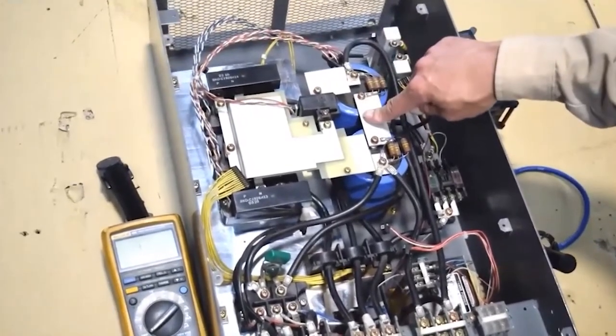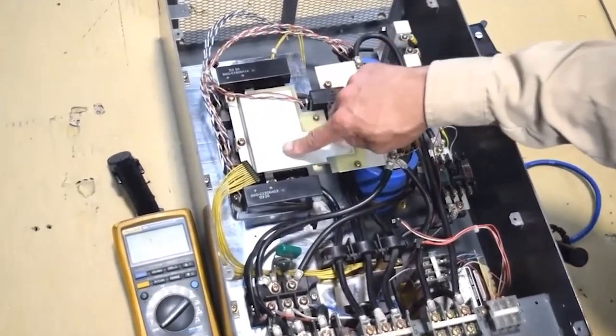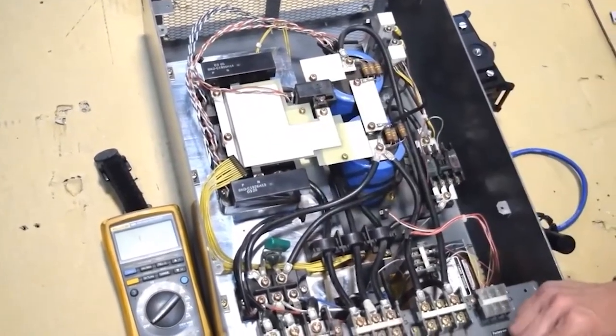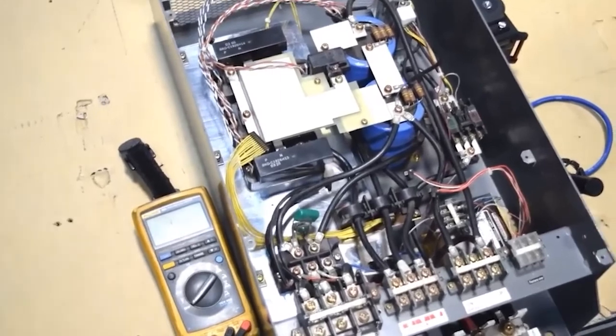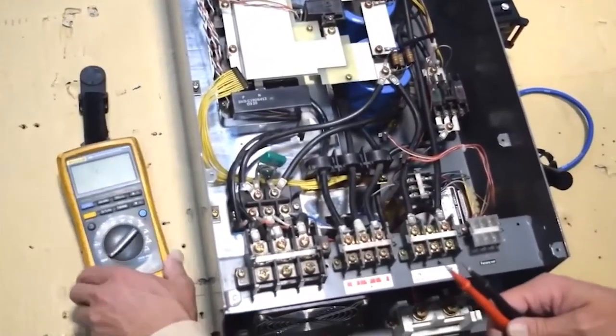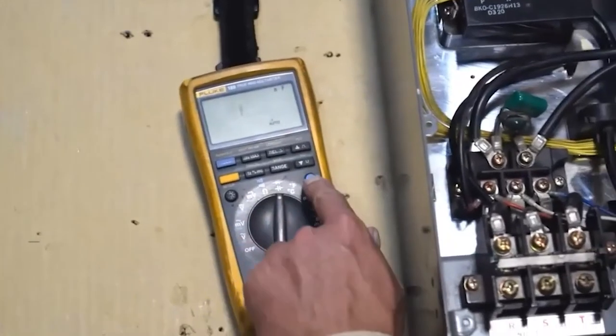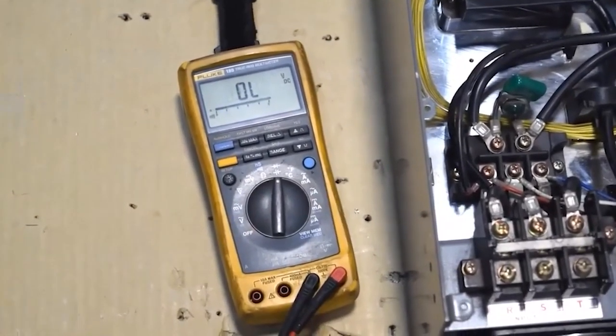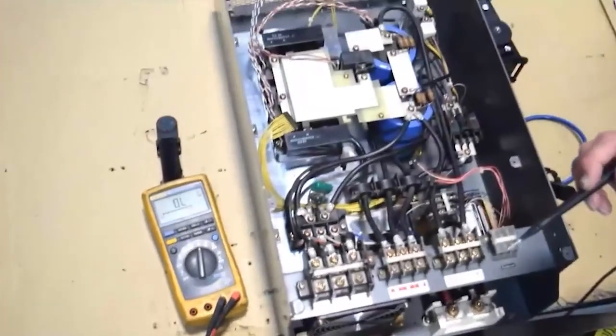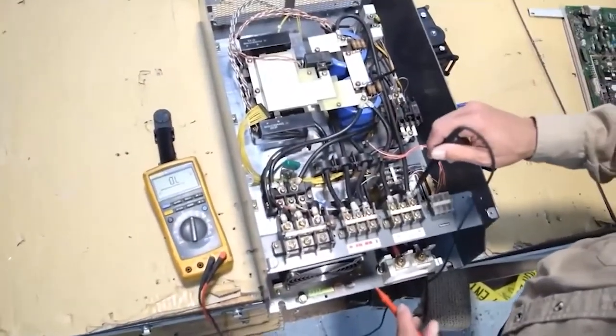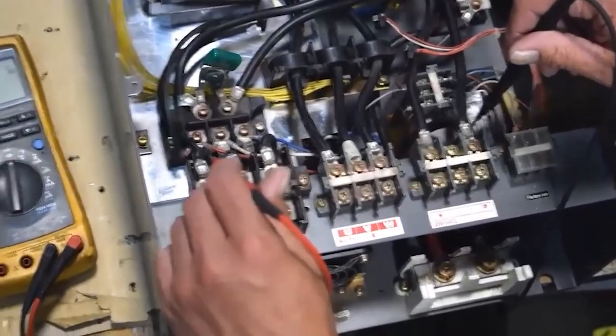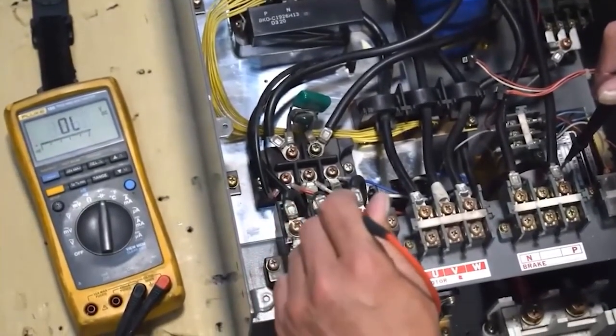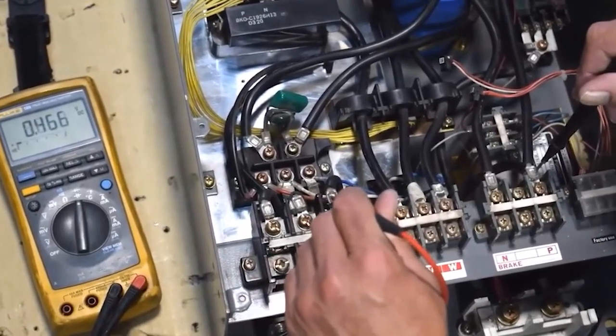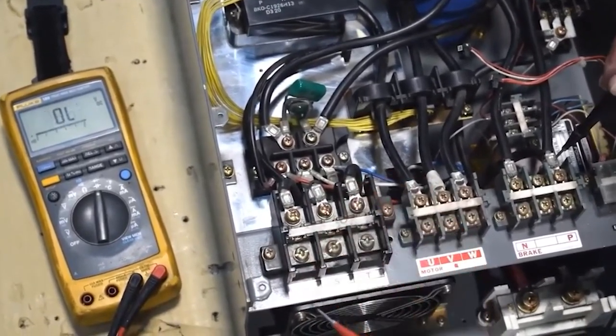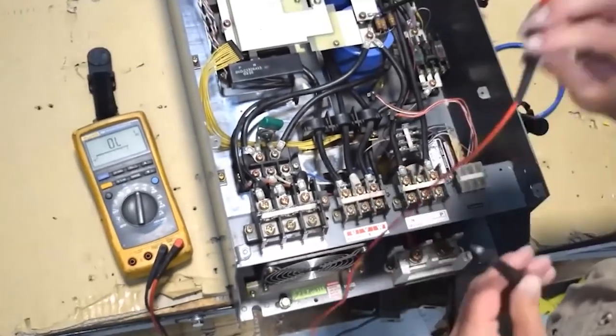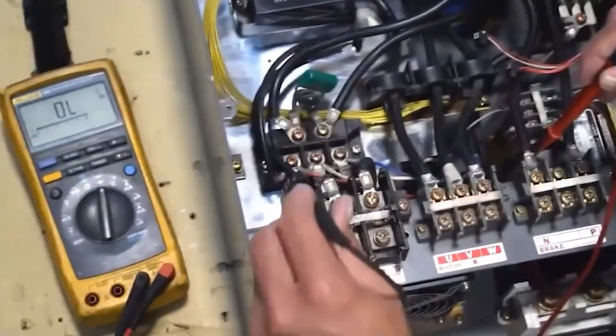So just to do a recap, you've got your rectifier module, pre-charge circuit, capacitors, and your inverter section, or your transistors. All right, now I'm going to proceed to do a diode check, similar to what we did on the other one. So I'm going to put my meter in diode mode, which is a little arrow. I'm going to take my negative lead and put it on my positive bus, and I measure all my incoming terminals. I'm getting 465 all the way across. Once again, between 0.2 and 0.5 is a normal kind of reading.